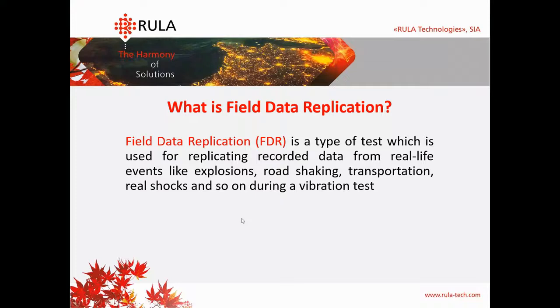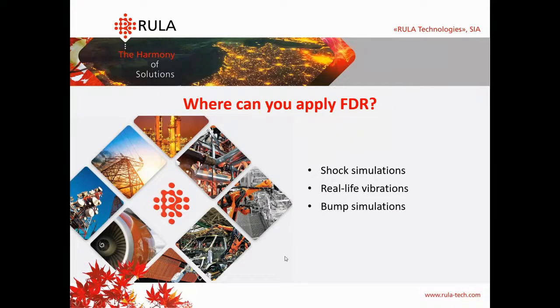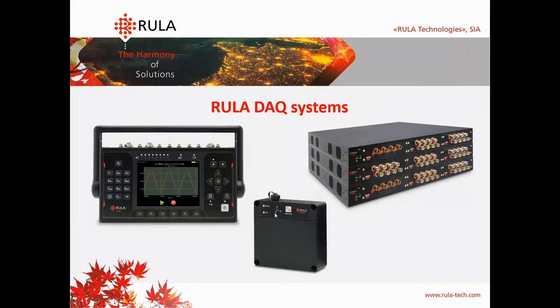First of all, what is field data replication? It's a type of test which is used for replicating recorded data from real-life events like explosions, road shaking, transportation, real shocks, and so on during a vibration test. Here you can see replication examples for field data replication — it can be used in shock simulations, real-life vibrations, and even bump simulations.